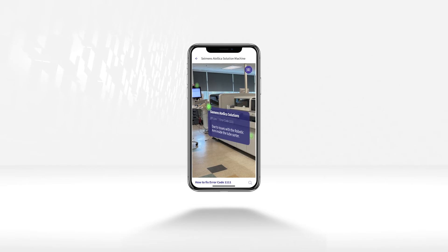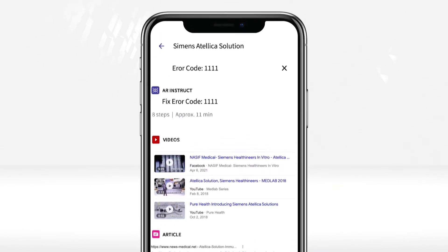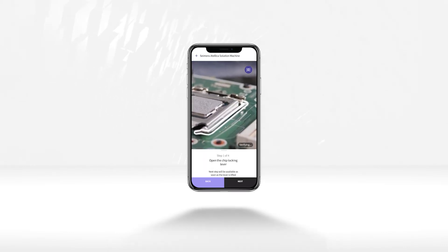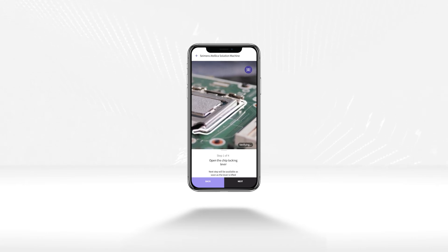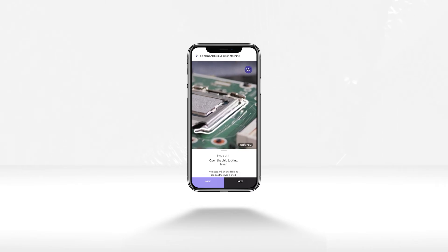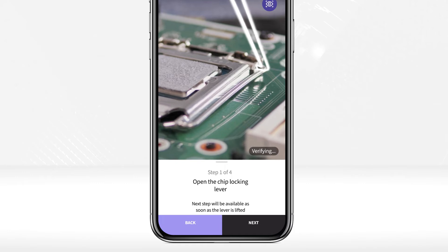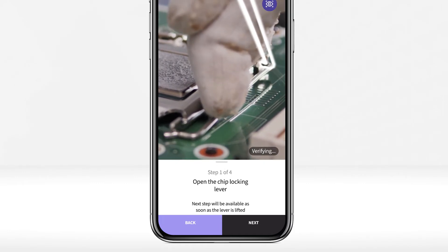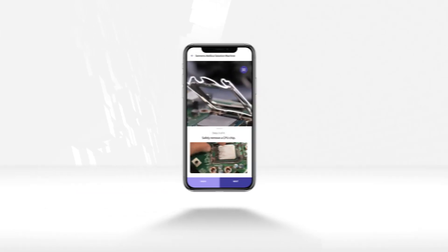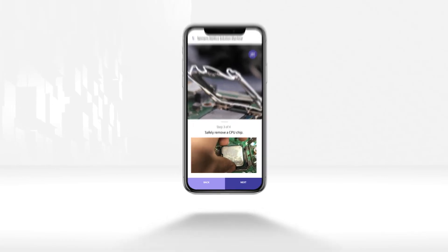Through the search panel, he can get instant access to relevant content including knowledge-based articles, videos, and step-by-step AR instructions so he can self-solve on his own. The issue has to do with a faulty computer chip inside the Atellica components. He follows the step-by-step instructions and using computer vision, CareAR visually and automatically verifies each step has been completed properly, and when needed can also display a video of the chip replacement process side-by-side.